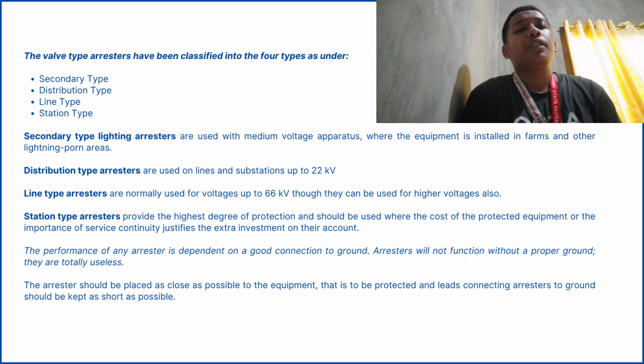It is also important to note that performance of any arrestor depends on a good connection to the ground. Without proper grounding, the arrestor will not function effectively. Lastly, the arrestor should always be placed as close as possible to the equipment it is meant to protect. And the ground connection should be kept short and direct to minimize resistance and improve efficiency.